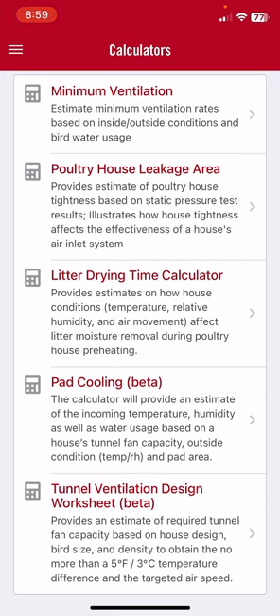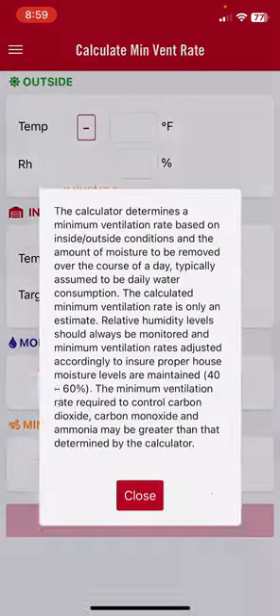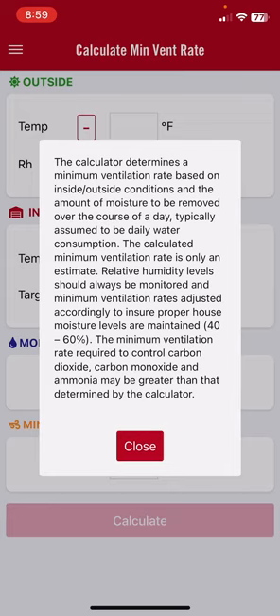To use the calculator, you click on minimum ventilation. A message comes up describing basically how the app works. The target with the minimum ventilation app is to control moisture. The fact is that 90 to 95 percent of the time, what we're trying to do in a poultry house is to control house moisture levels — not CO2, not oxygen.